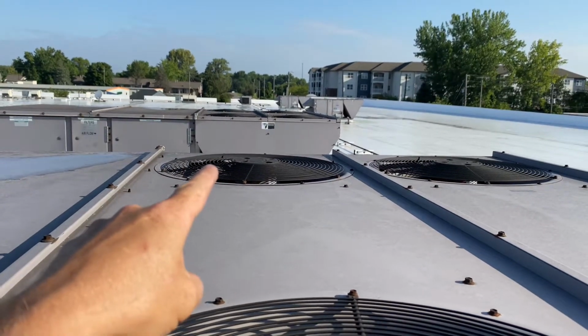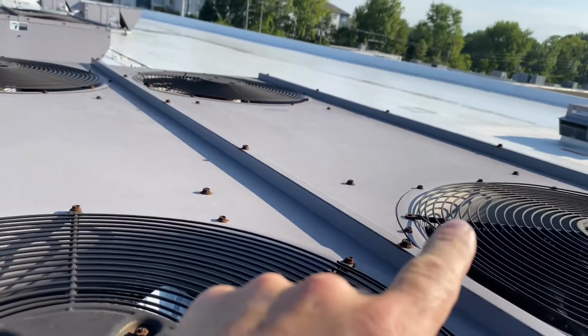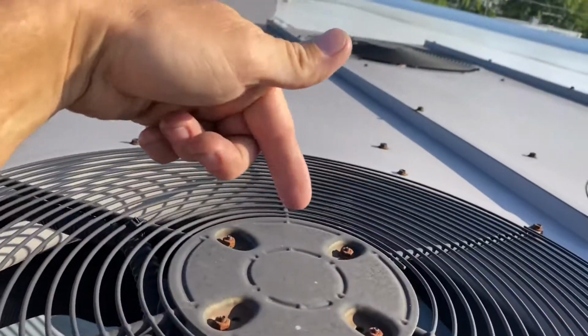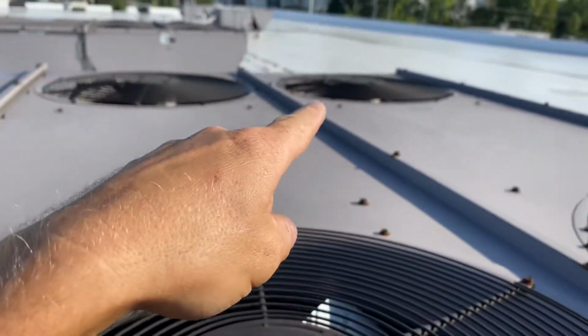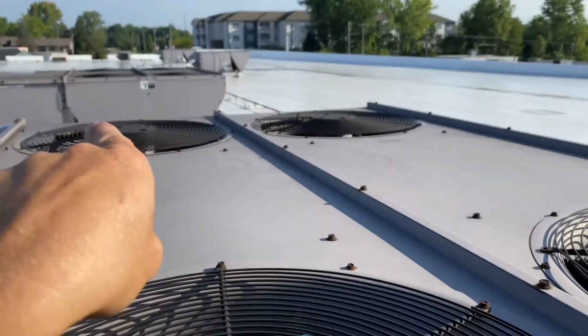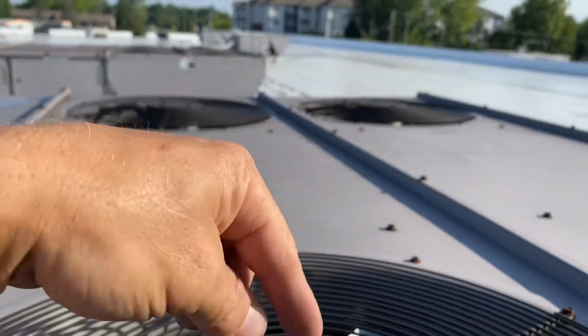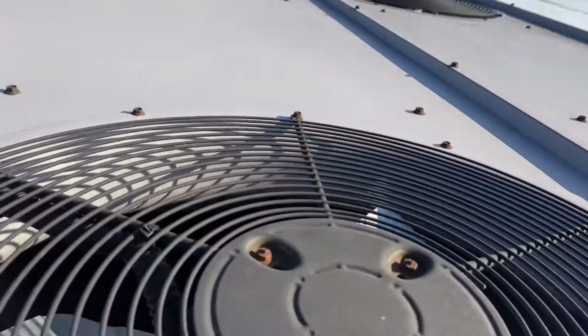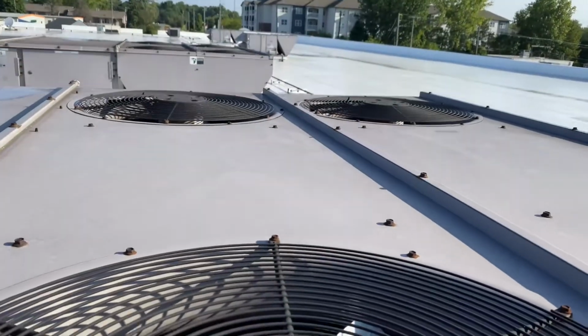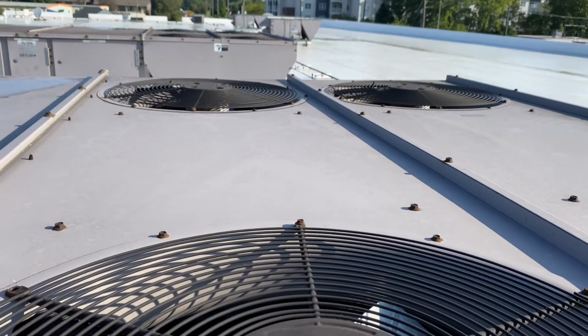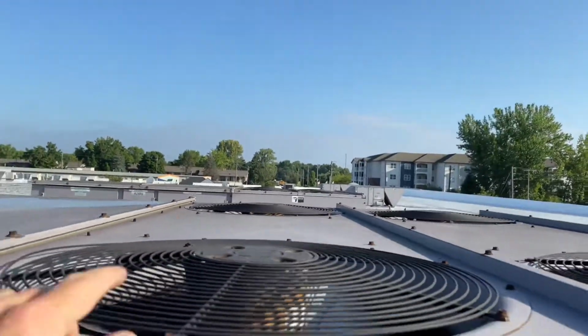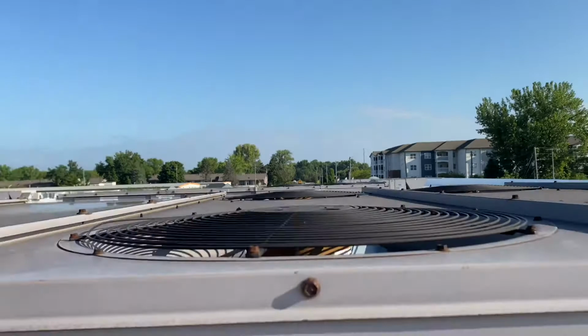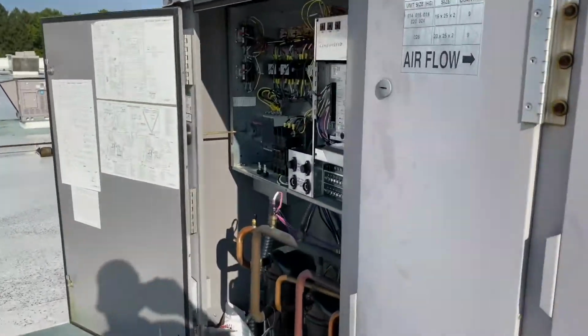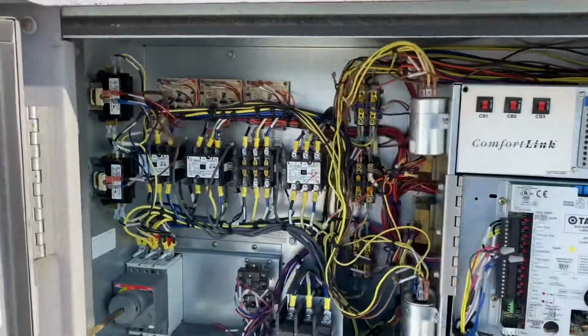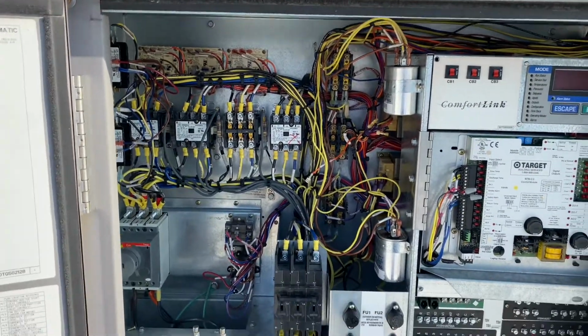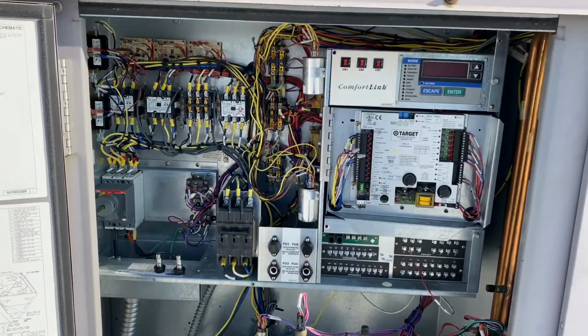So with this one unlanded at the motor, and this one unlanded at the motor, I will have basically fans 2 and 4. It goes 1, 2, 3, 4. So I'll have fans 2 and 4, which are opposite corners, which is the next step of the test anyway. And then once I have those unwired, like I say, I'll land the wires back on the contactors and then test all the contactors and make sure everything's good to go from there. If everything's good to go, I will be replacing those 2 motors.